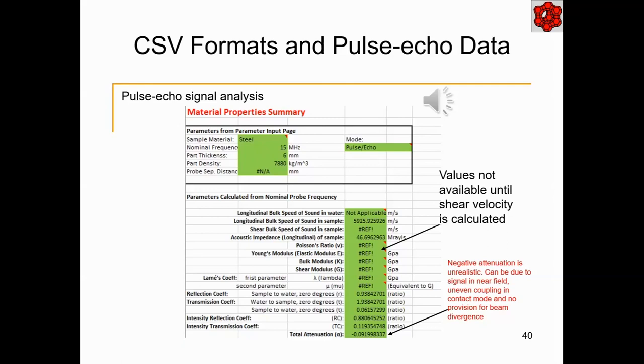If the waveform data collection had also included the use of SH shear wave transducers, it would be possible to collect two multiples of the thickness in shear mode. With shear mode velocity, other parameters can also be calculated. Running the spectrum analysis on the pulse echo data can provide an estimate of attenuation based on total energy in the two echoes and the reflection coefficient. Some of the other plots, such as phase velocity and attenuations, will not be valid.